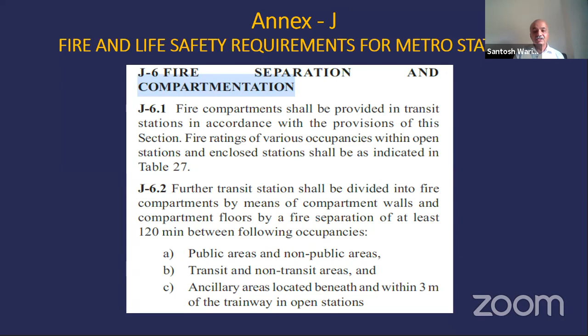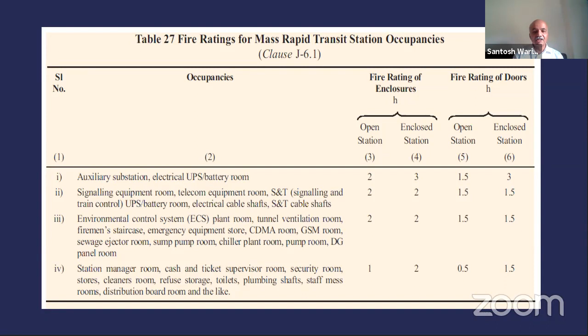So this is a table provided in that annexure, table 27, which speaks about the fire rating requirements in open stations and in enclosed stations. Also, it gives the requirement for fire rating doors in the open station and enclosed station. Enclosed station means underground metros. There are also auxiliary substations and electrical UPS rooms. There they have given the requirement for 2 hours and 3 hours fire rating for the enclosures. Then there are different station managers' rooms, and all details are given for these rooms.